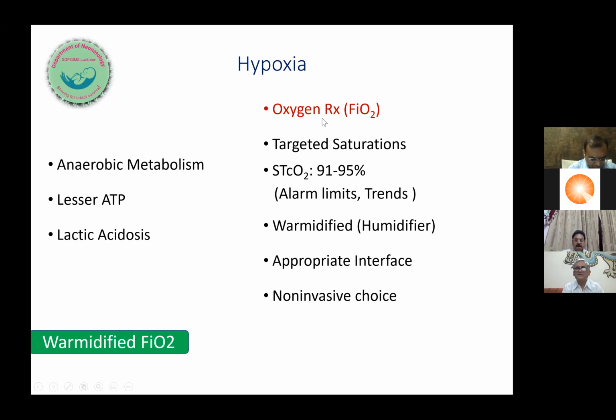And whenever we connect oxygen, we have to give oxygen to a desired level of saturation range. Today, across all gestation and age, we put a saturation limit between 91 to 95%. This should be remembered. Now, these alarm limits have to be kept in mind and must be put. The moment you start oxygen, set the alarm limit. And then once we come for a round, during night time, we should look at the trends, whether he dipped. Your nurse might say that he remained all right. But if we look at the trend of 24 hours, 48 hours, we'll come to know how good or bad the baby is doing. Okay. So oxygen trends, now we also call them oxygen histograms. So we should know them and look at them.